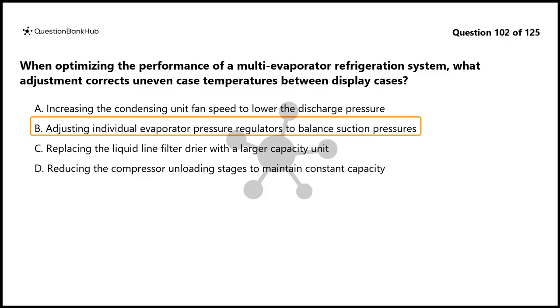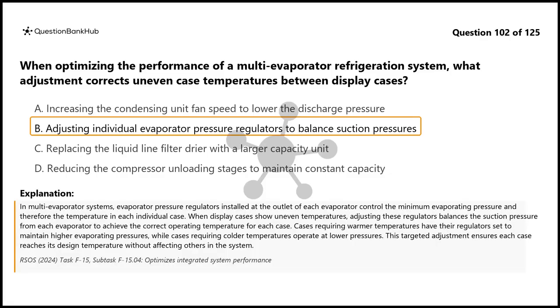The correct answer is B. In multi-evaporator systems, evaporator pressure regulators installed at the outlet of each evaporator control the minimum evaporating pressure and therefore the temperature in each individual case. When display cases show uneven temperatures, adjusting these regulators balances the suction pressure from each evaporator to achieve the correct operating temperature for each case. Cases requiring warmer temperatures have their regulators set to maintain higher evaporating pressures, while cases requiring colder temperatures operate at lower pressures. This targeted adjustment ensures each case reaches its design temperature without affecting others in the system.